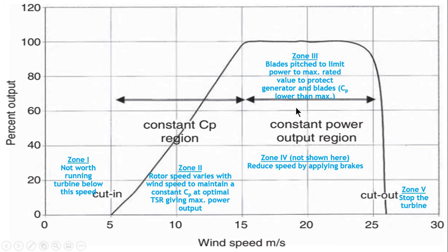Next is Zone 3, in which the blades are pitched to limit the power to maximum rated value to protect the generator and blades. The rotor efficiency is lower than the maximum rating in this particular area.